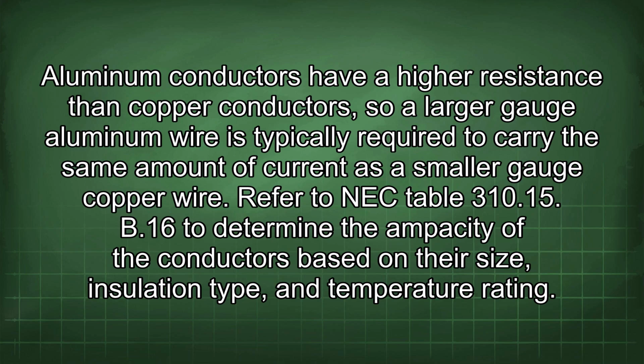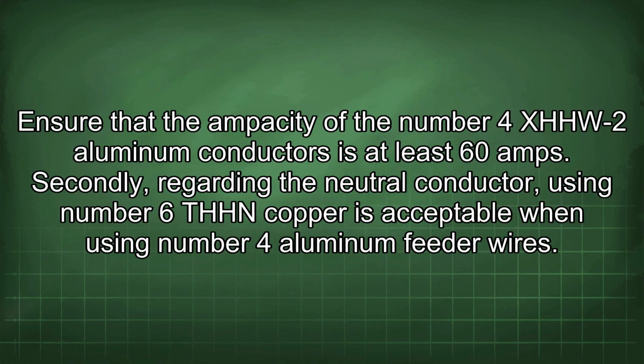Refer to NEC Table 310.15(B)(16) to determine the ampacity of the conductors based on their size, insulation type, and temperature rating. Ensure that the ampacity of the number 4 XHHW-2 aluminum conductors is at least 60 amps.